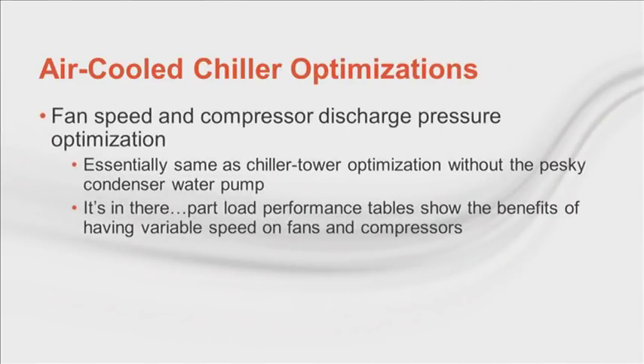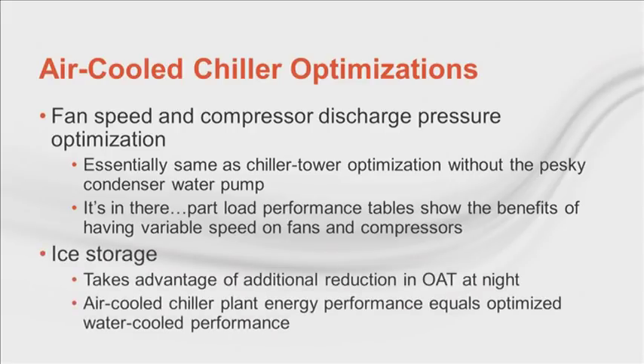Optimizations for air-cooled chillers rely on balancing condenser fan speed with discharge pressure. It's really the same as water-cooled, but with one less heat exchanger, no condenser water pump, and done by the chiller controller. The chiller part load performance data shows the benefits of both variable speed condenser fans and staged and/or variable speed compressors. Another optimization for air-cooled chillers is thermal storage.